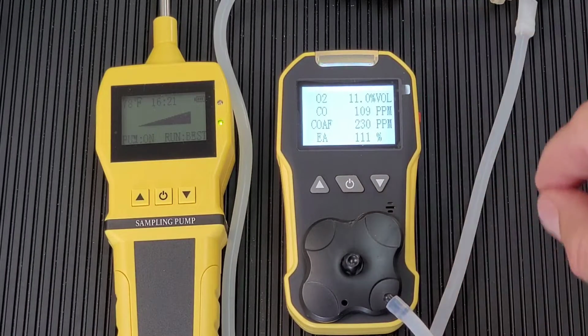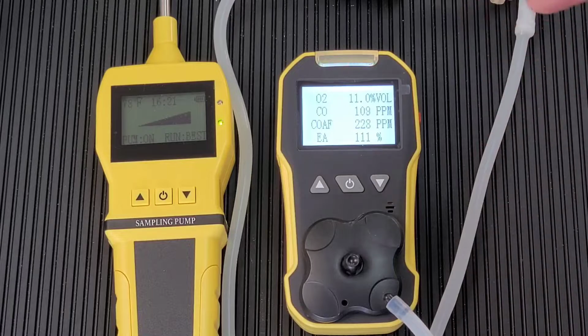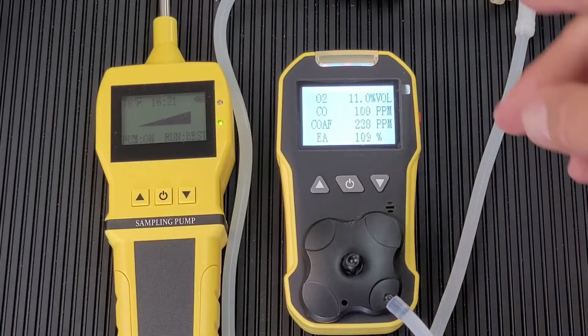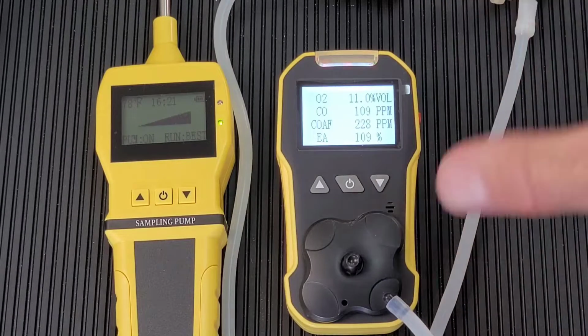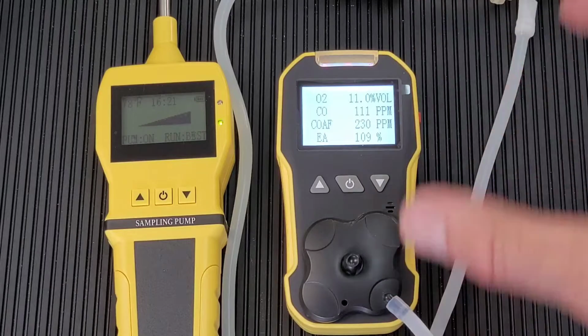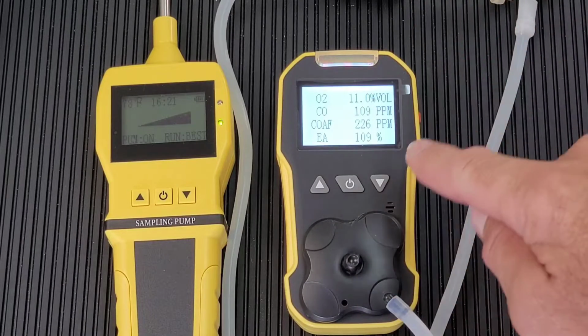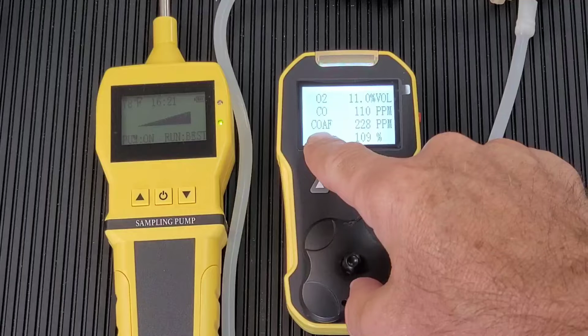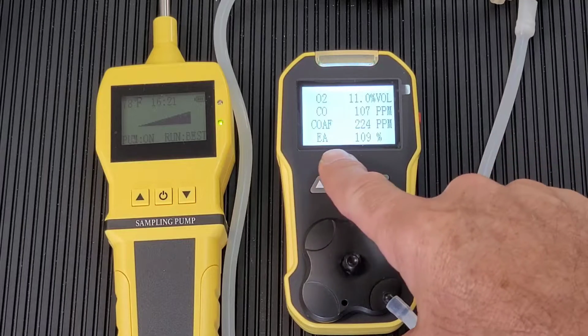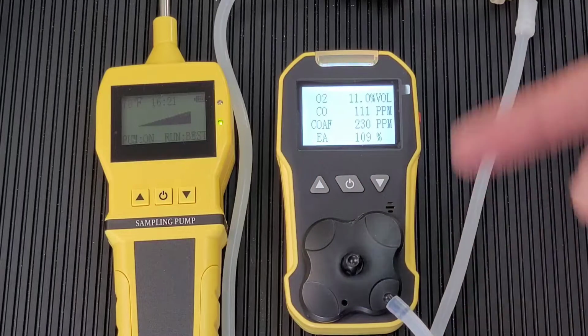Still going down a little bit, but it's in that region, definitely within specification, and definitely more than acceptable when it comes to a combustion measurement. As we could see now, you can also see the COAF being calculated and the excess air being calculated on the run continuously.